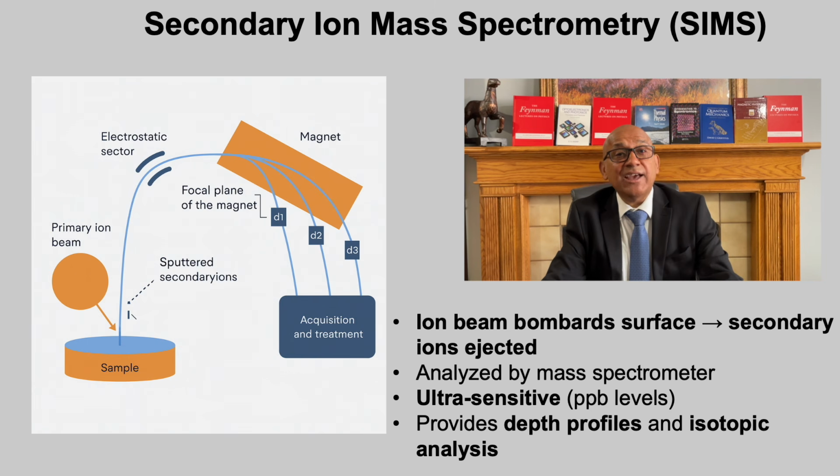Because the signal strength extends to parts per billion, SIMS is the most sensitive of all compositional probes. By continuously sputtering while recording spectra, we can obtain depth profiles with nanometer resolution, ideal for dopant distribution in semiconductors or multi-layer films. However, SIMS is destructive, and quantification requires standards. In combination with XPS and EDX, it complements the chemical composition picture from surface to bulk.